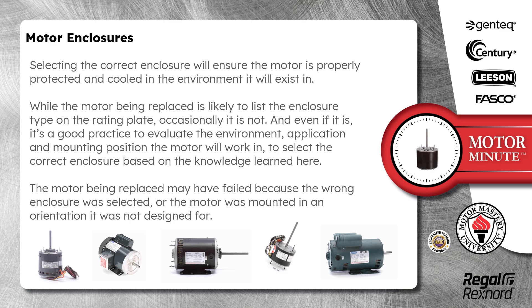Selecting the correct enclosure will ensure the motor is properly protected and cooled in the environment it will exist in. While the motor being replaced is likely to list the enclosure type on the rating plate, occasionally it is not. And even if it is, it's a good practice to evaluate the environment, application, and mounting position the motor will work in to select the correct enclosure based on the knowledge learned here. The motor being replaced may have failed because the wrong enclosure was selected or the motor was mounted in an orientation it was not designed for.